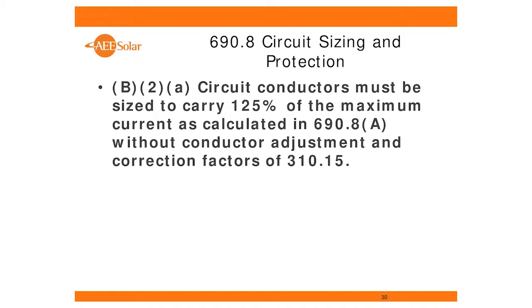So this talks about how much you have to oversize your conductors and things like that based upon the current that you calculated in 690.8(A). So 690.8(A) determines what is maximum circuit current. So maximum circuit current for a source circuit, a PV source circuit, is the rated short circuit current of the modules in that string times 125%. Well, that's a very conservative number, by the way. All right? And that's considered the current, and then we have to design our wire to be able to handle that as a continuous current. So we have to actually add another 125% on top of that. That's what this particular 690.8(B)(2)(a) says.